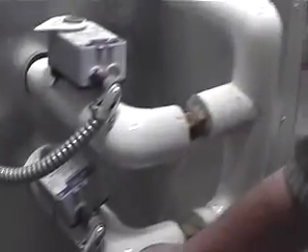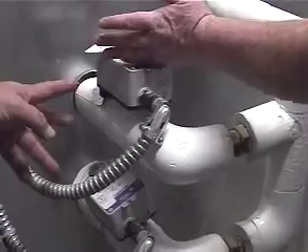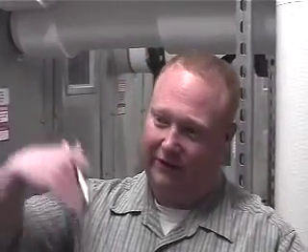So let me give you a little bit better idea of how this works. When we go to the evap mode, and we'll talk a little bit more about that on the computer, the first thing we do is we shut the drain valve. We then open the makeup valve. The makeup valve then stays open. We have a timer in there, it's set for 15 minutes. So we just let the system run for 15 minutes, and that just fills the pan up. After the 15 minutes, we fire the pump. Now we're dumping water over the system.